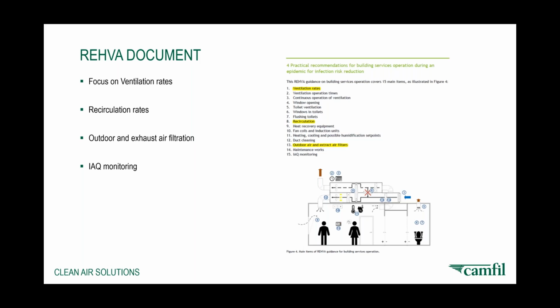What it says is that you need to focus on the ventilation rates, and they've given guidance on the ventilation rates and the number of air changes that are required in rooms, etc. They've given specific advice on recirculation and outdoor and exhaust air filtration and the use of indoor air quality monitoring. So particle counts, indoor air quality assessments by validation companies, by the correct professionals, etc. It's well worthwhile getting this document and reading it in full because there's some good advice here.